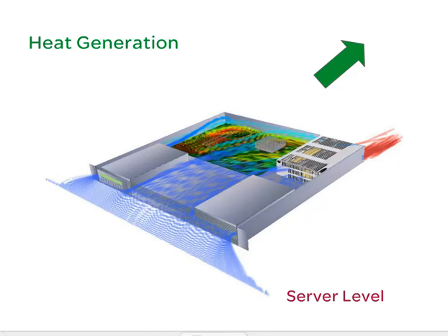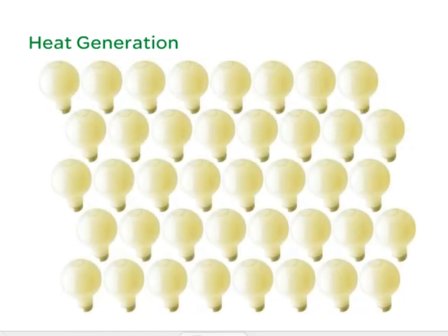The amount of heat generated by servers is on a rising trend. A single blade server chassis can release 4 kilowatts or more of heat energy into the IT room or data center. Such a heat output is equivalent to the heat released by 40 100-watt light bulbs, and is actually more heat energy than the capacity of the heating element in many residential cooking ovens.